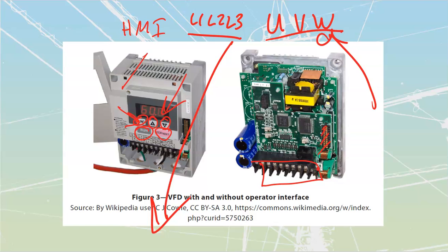We've also got, in some cases, the ability to plug these onto a network, where we're going to have network communications done either through serial, or through Ethernet, and at times even through coaxial, although those systems are pretty old and pretty much out of there. If I've got a bunch of drives to program as well, a lot of them carry their memory on just these little memory cards. Sometimes they're SD cards that you can insert into these to carry that memory from one to the next. But other ones are going to have other types of non-volatile memory.